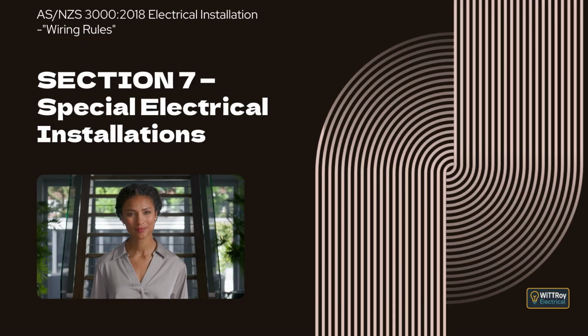Clause 7.2.4.2 Arrangement of main switches. This clause explains how main switches for safety services must be arranged. It states that they must be connected on the supply side of all general electrical installation main switches, must not be subject to the control of any general electrical installation main switch, and must control only electrical equipment that is regarded as safety services. The clause then explains that this requirement does not need to apply to certain situations, including high-voltage switches supplying low-voltage switchboards that are not regarded as general installation main switches, low-voltage switches that can only be operated by authorized persons and are clearly marked, safety services installed in individual or combined outbuildings or fire-separated portions of a building, and certain automatic fire detection, alarm, sound and intercom systems provided they meet the stated supply, marking and secondary power source requirements.